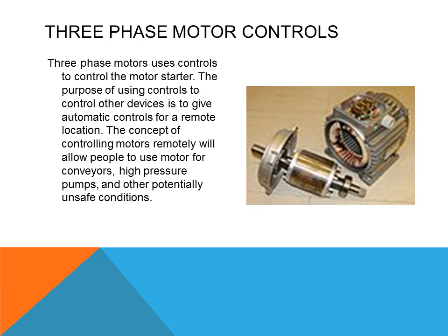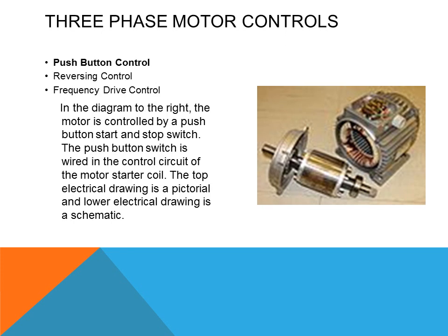Three-phase motors use controls to control the motor starter. The purpose of using controls to control other devices is to give automatic control for a remote location. The concept of controlling motors remotely allows people to use motors for conveyors, high-pressure pumps, and other potentially unsafe conditions. In the diagram to the right, the motor is controlled by a push button start and stop switch. The push button switch is wired into the control circuit of the motor starter coil. The top electrical drawing is a pictorial and the lower electrical drawing is a schematic — the schematic is a simplified, easy-to-understand representation of how current flows, while the pictorial shows exactly how all the components are connected.